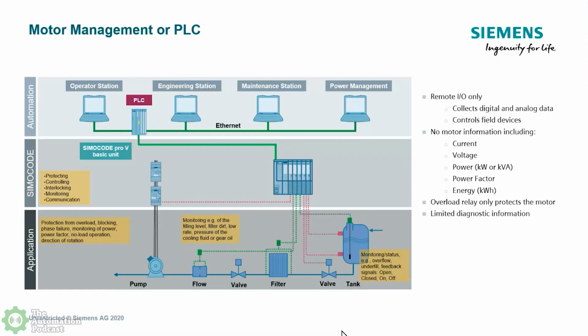But really, it's trying to emphasize that you're not getting any really major data to help you. And as you know, data is king nowadays. I know a few major applications out there that are looking for data right down to the IO point. But what we have here really is just an overload relay protecting the motor. And yes, you may have a sealing circuit or a contactor telling you that the three phases are pulled in and saying that it's running. But then of course you see the flow, so that tells you that the pump's operating and there's no coupler problem between the motor and the pump. And then you have a delta P, and that's coming in, but it's going to all this IO that's out there.